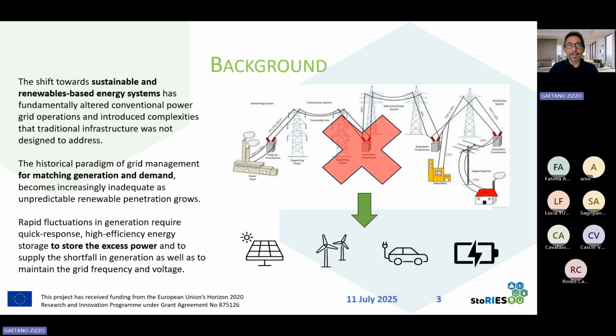And in many cases, and Italy has various examples of these cases, the connection of new renewable units has been limited by the distribution system operators worldwide because the protection of the grid was not ready for reverse power flow situations. This is only an example, but the first and the most important thing is that due to the increase of renewables, due to the increase of new loads, like, for example, electric vehicles, the historical paradigm of grid management for matching perfectly generation and demand has become increasingly inadequate.